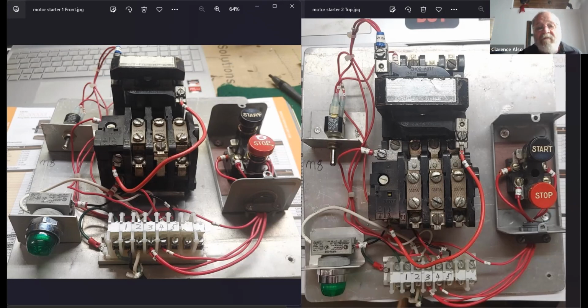So if you put 120 volts on number 5 above, and since the overload's not tripped, that'll give you 0, that coil is going to pull in. And we may be asking to check on the 6 side of the coil and the 2 side of the overload, based on what the symptoms are at the time.